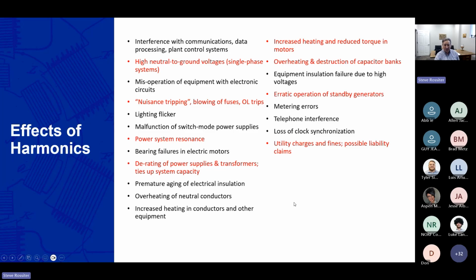In single phase loads, you probably remember when cubicles in office buildings were burning up. Those were because of so many computers being added and having a high level of third harmonic neutral to ground, which they actually changed electrical code to say you have to oversize those. So that was probably something everyone who has been in the electrical field of codes is aware of. Nuisance tripping with blowing of fuses or overloads.